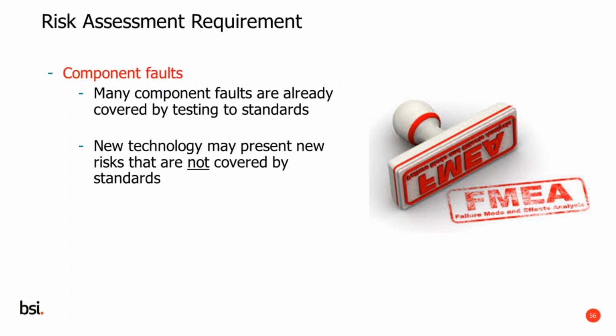One event I was involved in some years ago concerned a boiler which had an independent control thermostat and an independent overheat thermostat, as required by the standard, but they were both held on by a single screw. That screw failed, and both thermostats failed at the same time, leading to the product becoming unsafe.